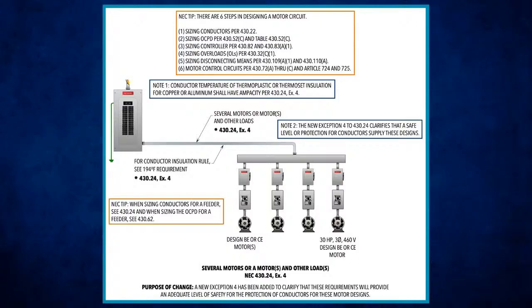When you look at that, there are some rules, but we put a tip at the top of this illustration with 6 steps for designing, taking you to 430.22 for the conductors, the overcurrent device, the controllers, and the overloads. Just follow through this and it'll get you through what you need to do. Basically it's the same as designing a regular one.